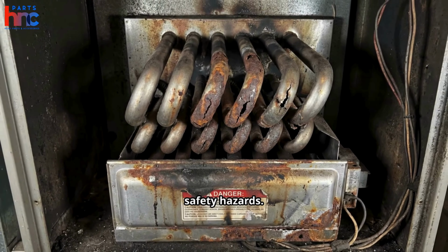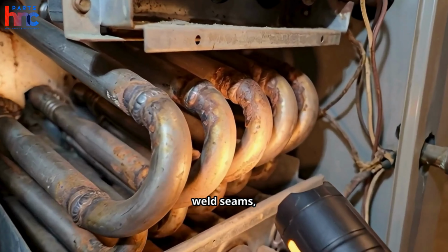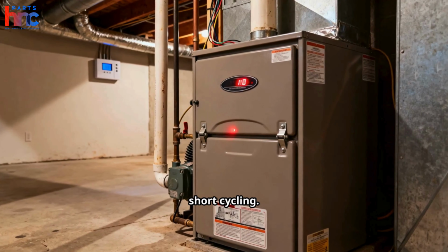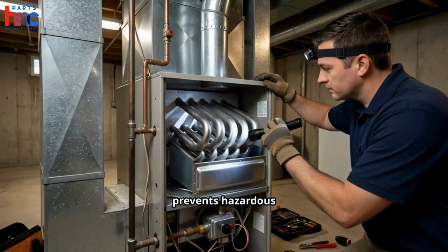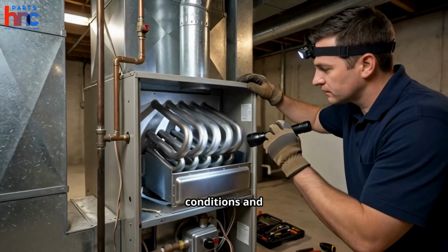Key warning signs of a failing heat exchanger include moisture or condensation inside the furnace, rust in supply ducts, backdrafting exhaust gases, corrosion especially around weld seams, and unusual furnace short cycling. Early detection prevents hazardous conditions and expensive repairs.